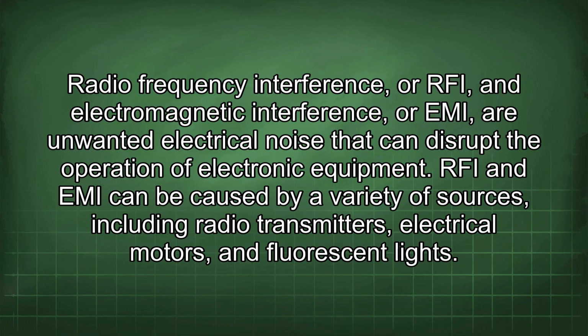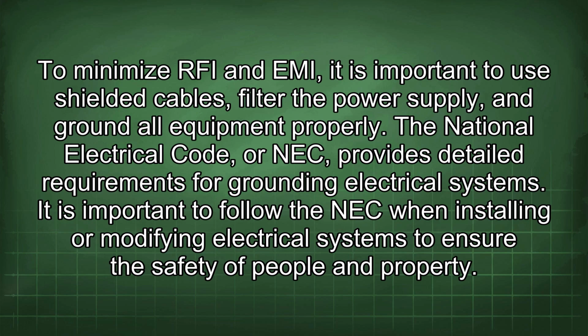Radio frequency interference, or RFI, and electromagnetic interference, or EMI, are unwanted electrical noise that can disrupt the operation of electronic equipment. RFI and EMI can be caused by a variety of sources, including radio transmitters, electrical motors, and fluorescent lights. To minimize RFI and EMI, it is important to use shielded cables, filter the power supply, and ground all equipment properly. The National Electrical Code, or NEC, provides detailed requirements for grounding electrical systems. It is important to follow the NEC when installing or modifying electrical systems to ensure the safety of people and property.